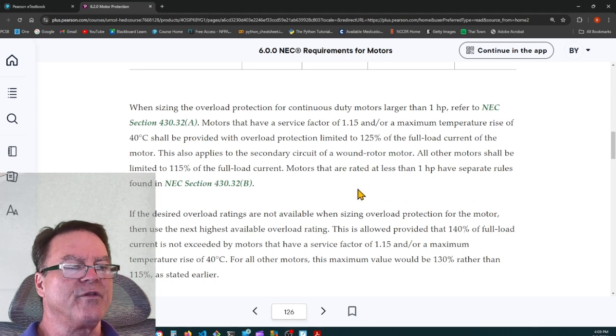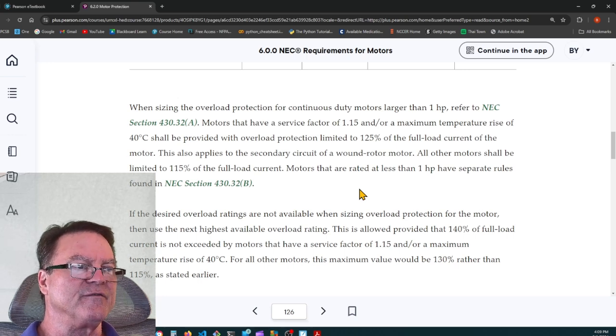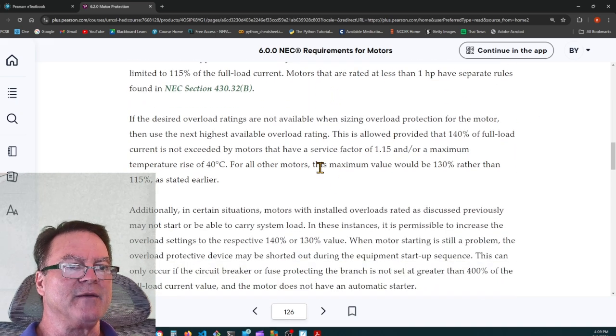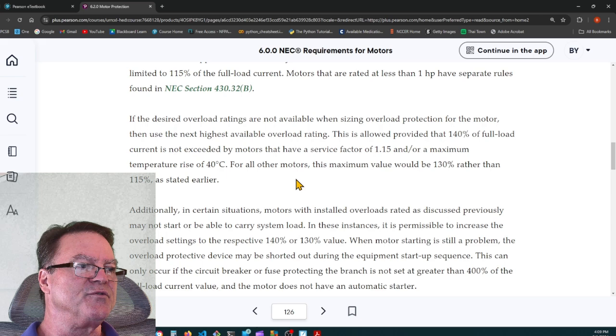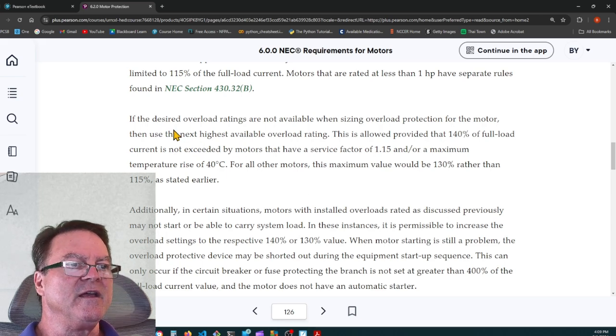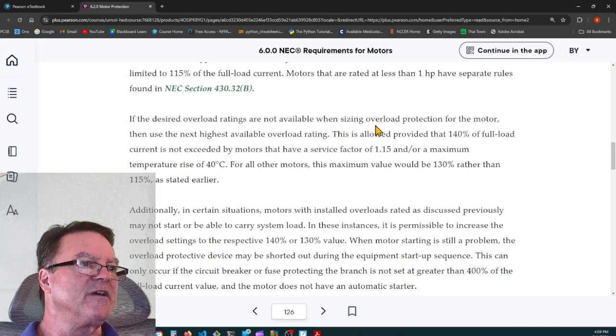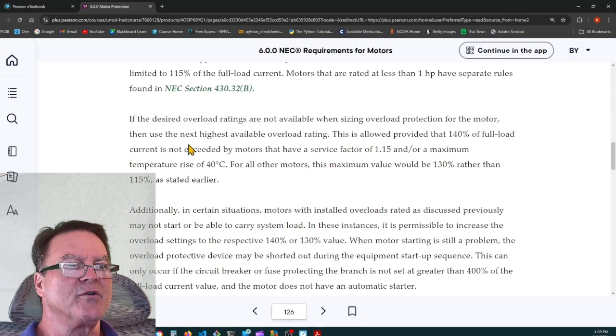And also, if you go to 430.6, it's going to tell you that you need to use the nameplate rating for the full load current to size the overloads. Most everything else, you can use the table values, 430.247 through 250. If the desired overload ratings are not available when sizing overload protection for the motor, then use the next higher available overload rating.